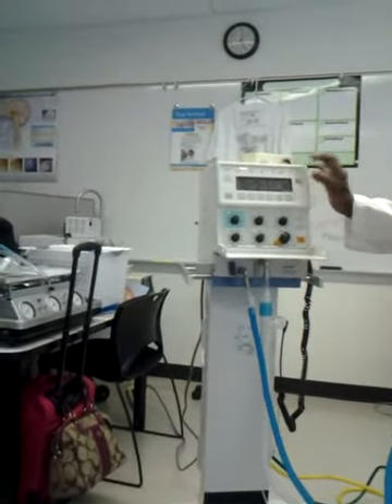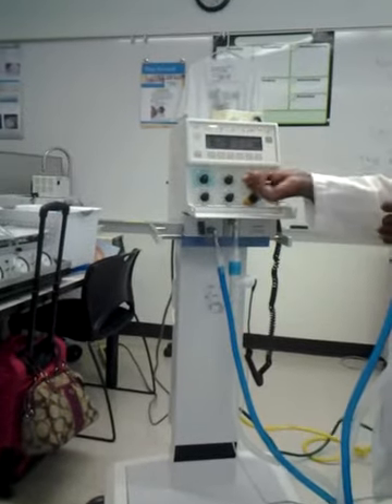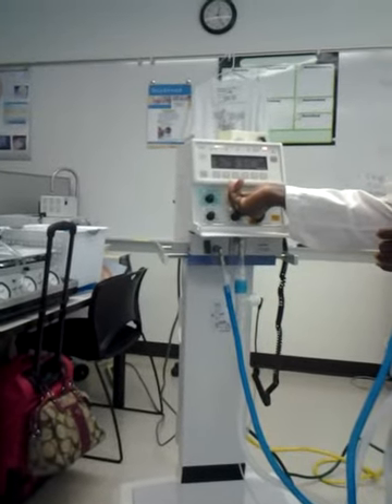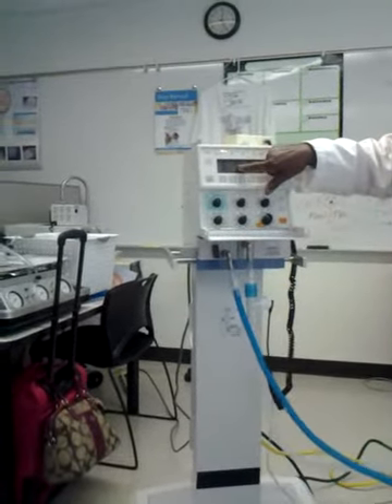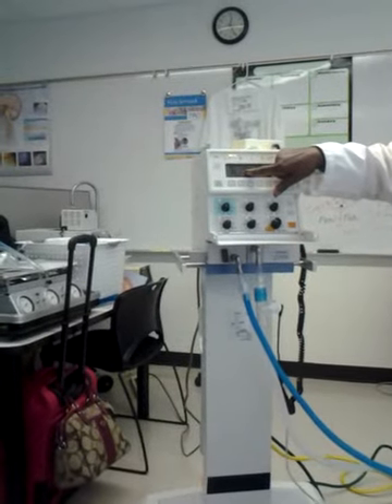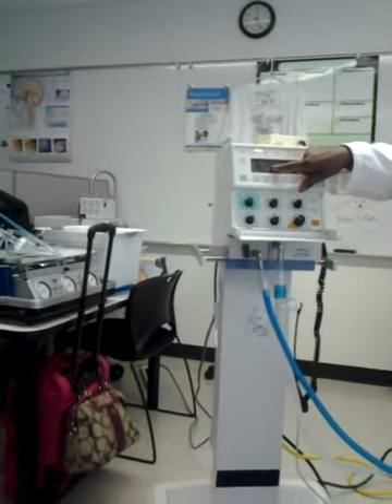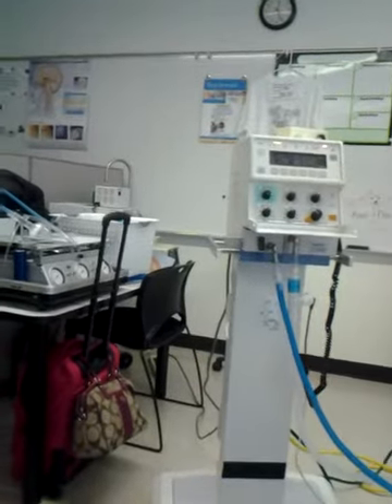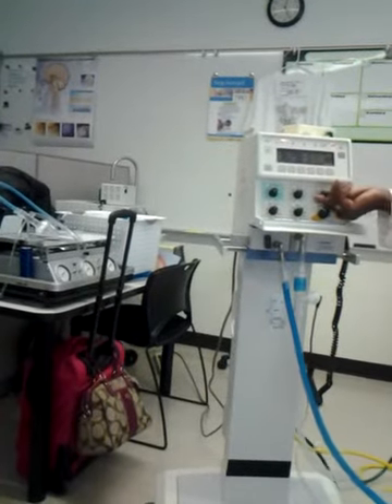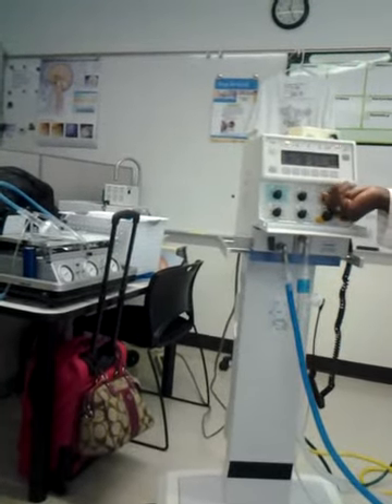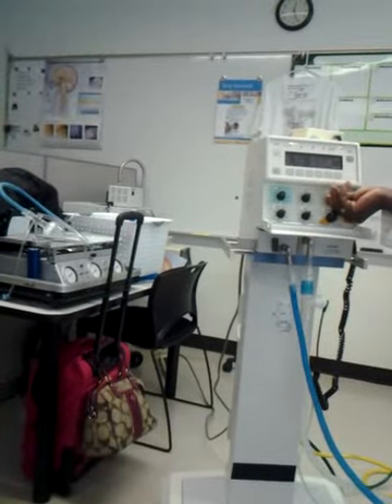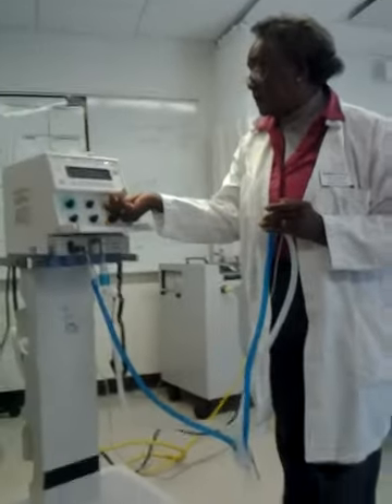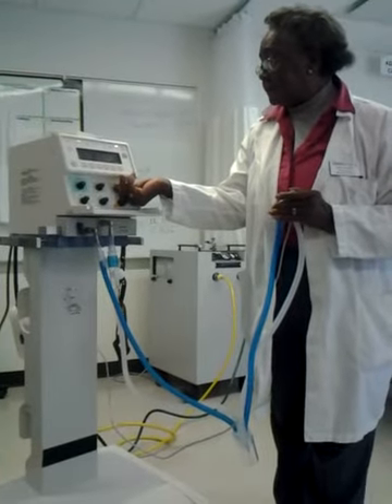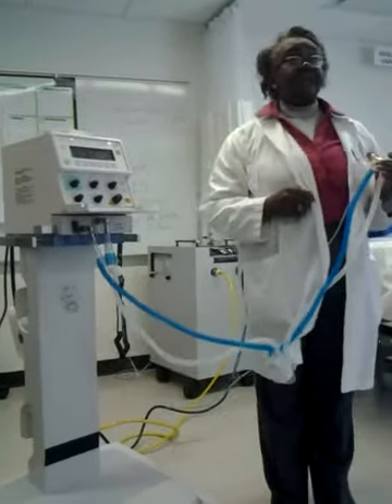So if I put my I time down to 0.4, some of you may have noticed that my respiratory rate changed to 28, from 24 to 28. Now, if I want to go back to 24 breaths per minute, I have to change my E time. And by moving my E time, I'm now back to 24 breaths per minute.